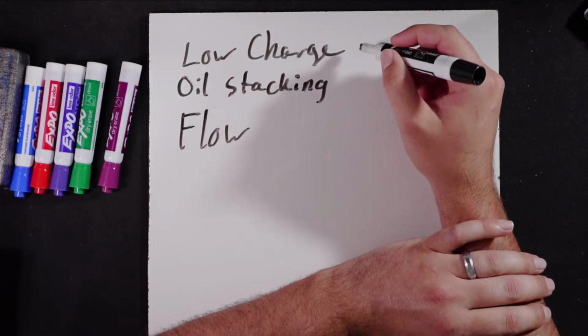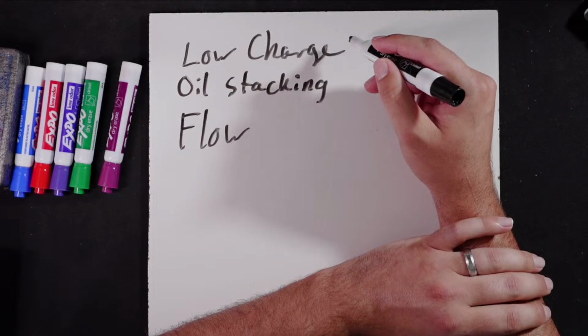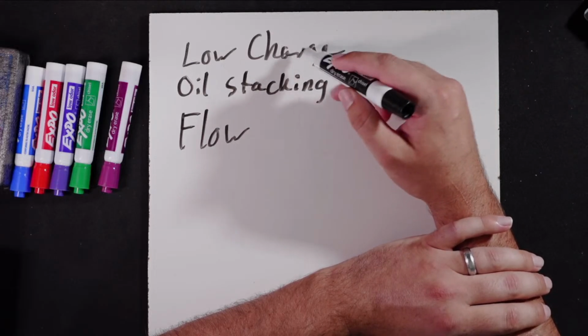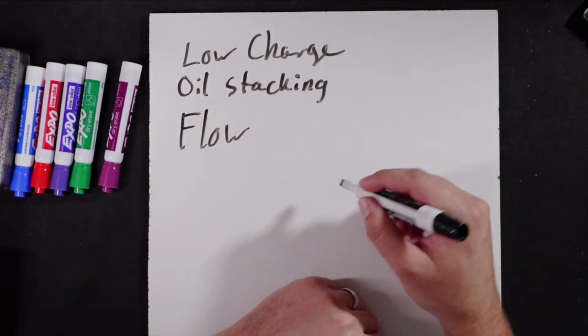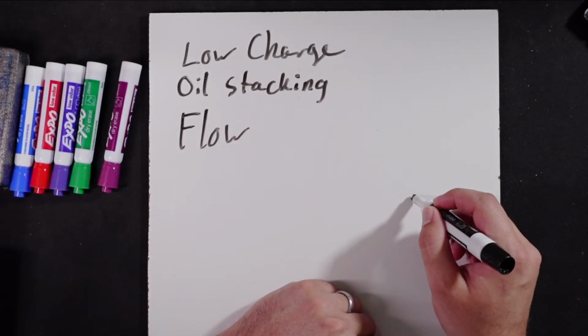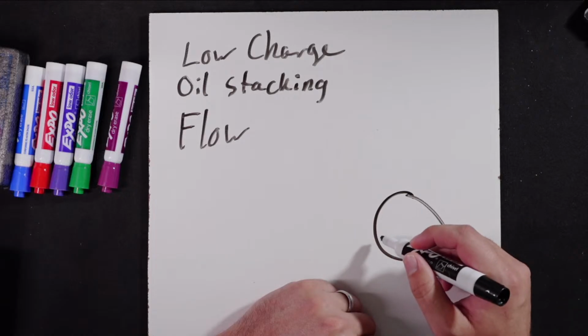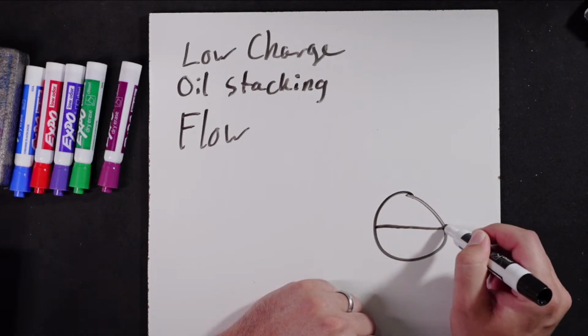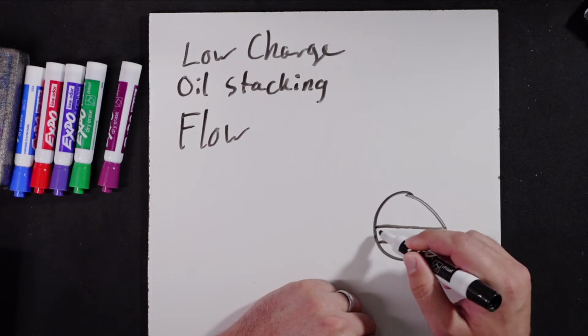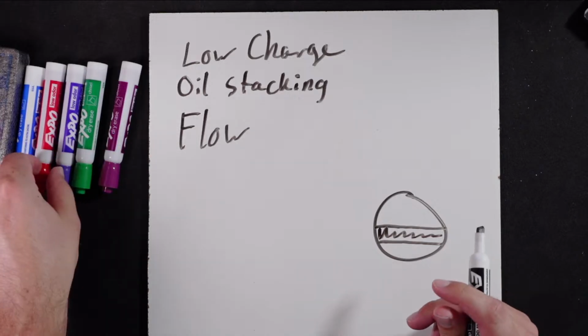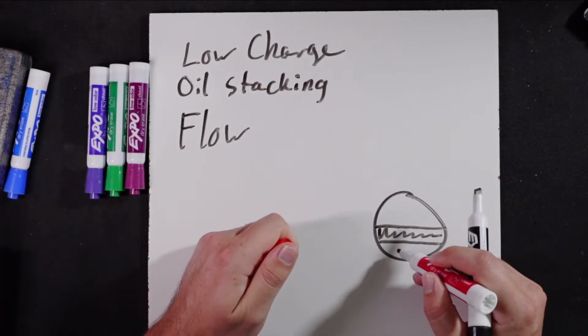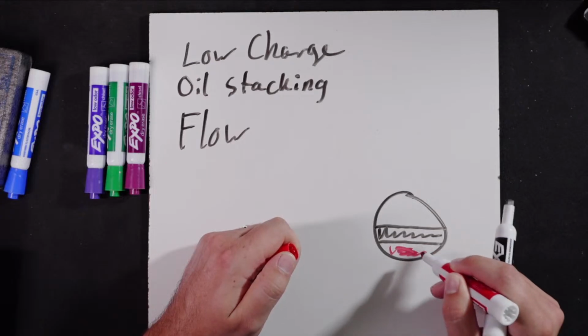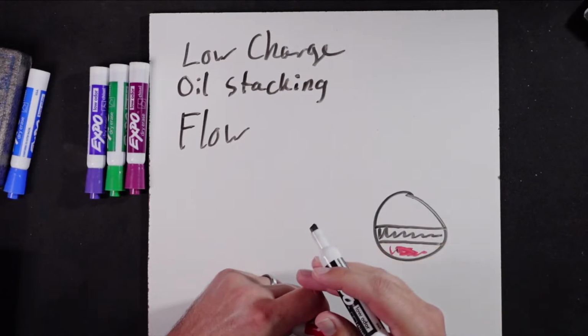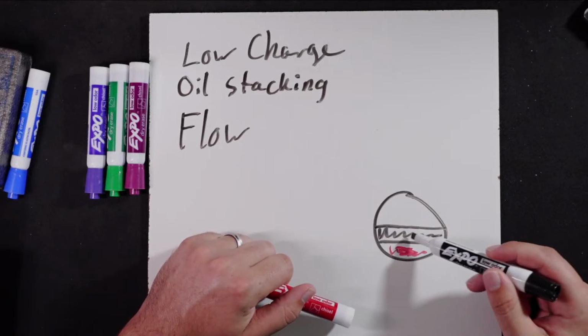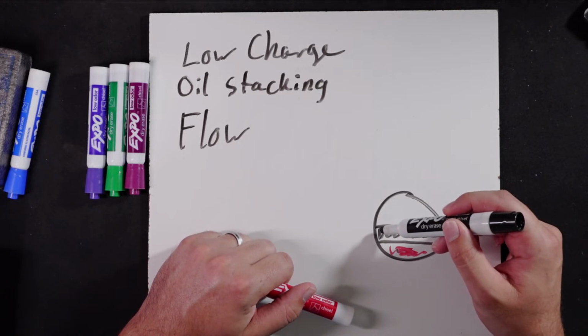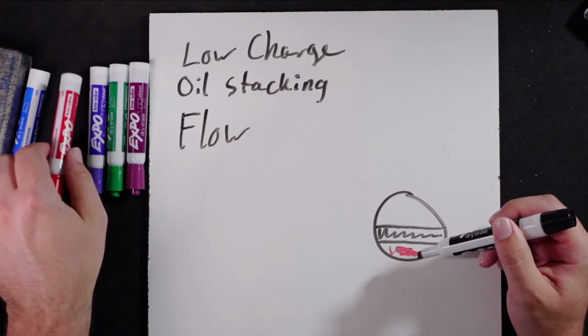So the charge, like I said, with the condenser valve, being that it's both circuits, I wouldn't think this was as likely. And in this, you're probably going to see that the evaporator sight glass is low. If you have your sight glass on each circuit, most of the time somewhere between, say, a half to about a third is normal. And if you get down below that, or it's not even in the sight glass in some cases, that's where you're going to see a problem. So my gut would tell me that I would expect to see, with suction limiting, low liquid level.